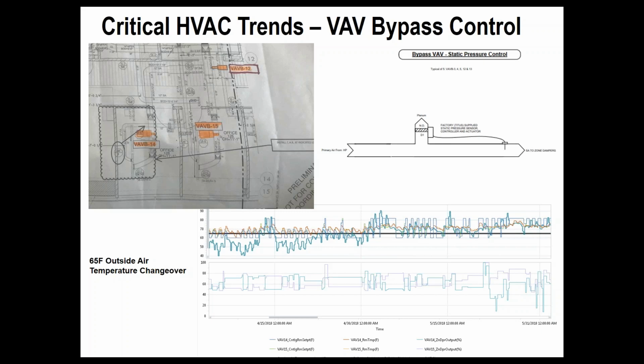So as Shannon mentioned, we went from a relatively simple system to, not a super complicated system, but a somewhat unusual system. There's a level of complication to it for sure. We have 2 individual offices in certain cases, served by one heat pump. So the internal loads of those two spaces aren't always exactly the same. So the way that AKF approached that was to provide VAV boxes downstream of the heat pumps.